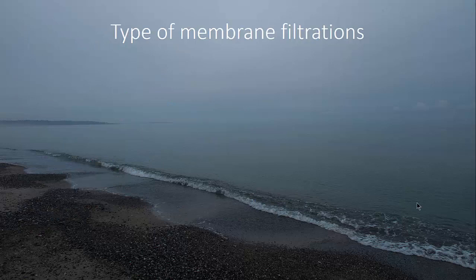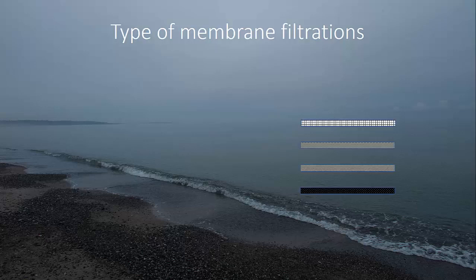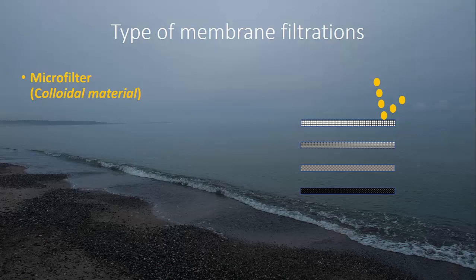What type of membranes and filtration possibilities do we have? There are four types represented by four rectangular bars. The first is microfilters. Microfilters remove colloidal material — very fine particles that don't settle by gravity and can't be removed by sedimentation. These can be removed by microfilters. Talking about membranes for water treatment, microfilters are rather coarse.